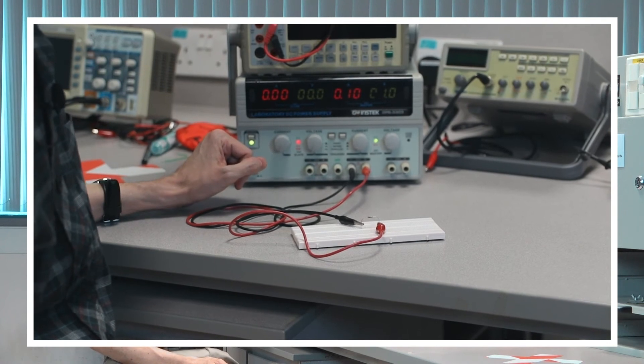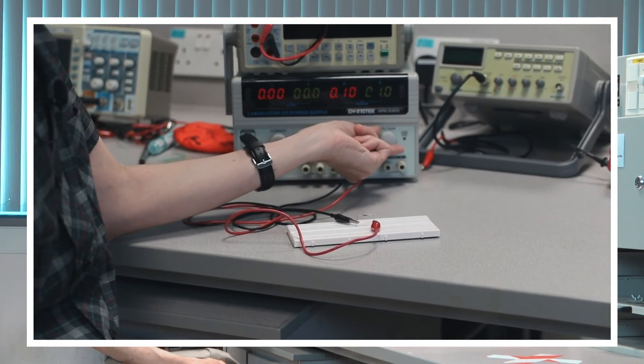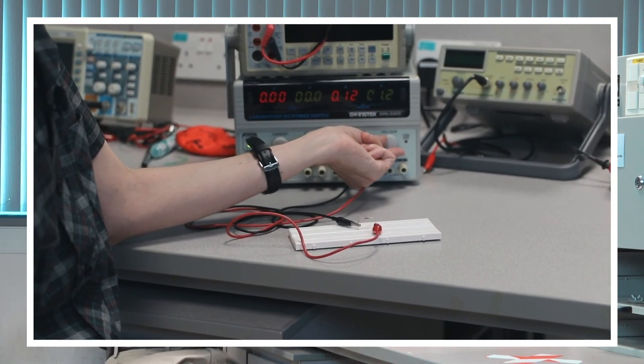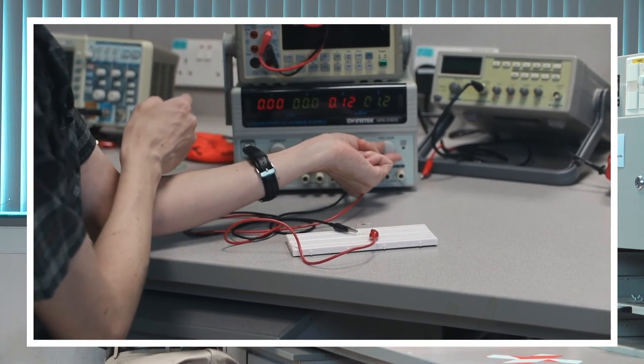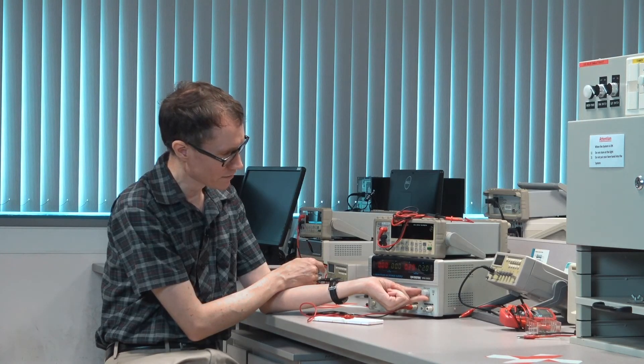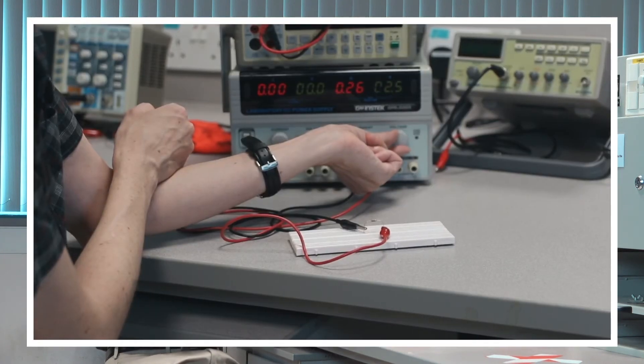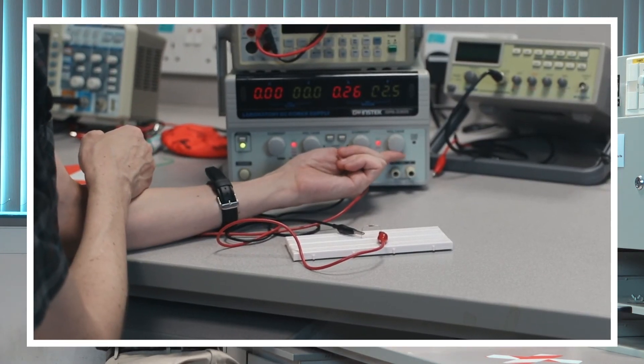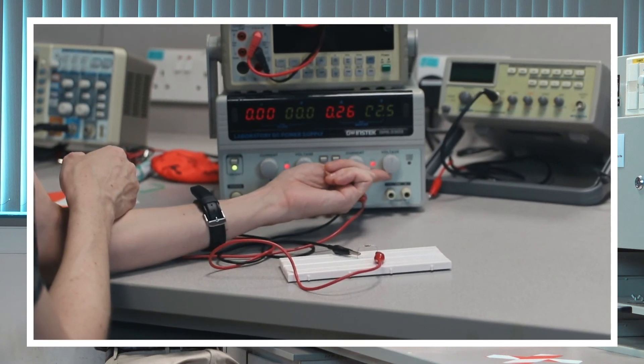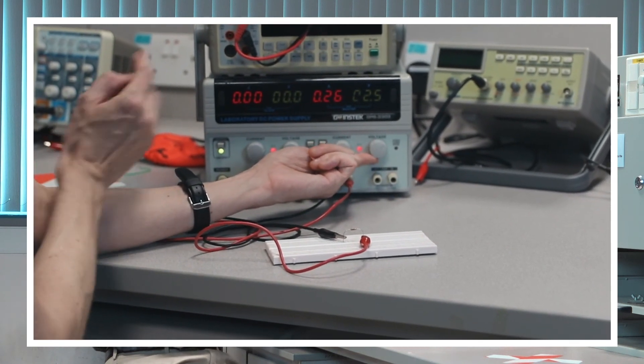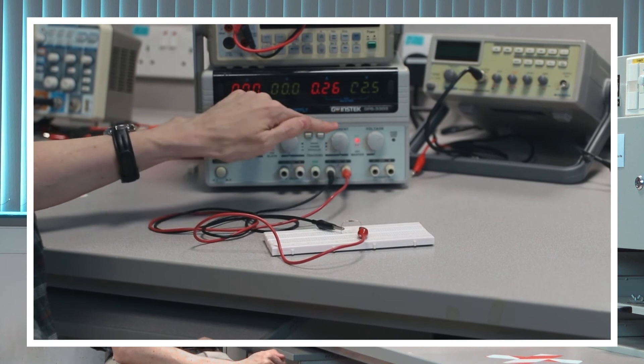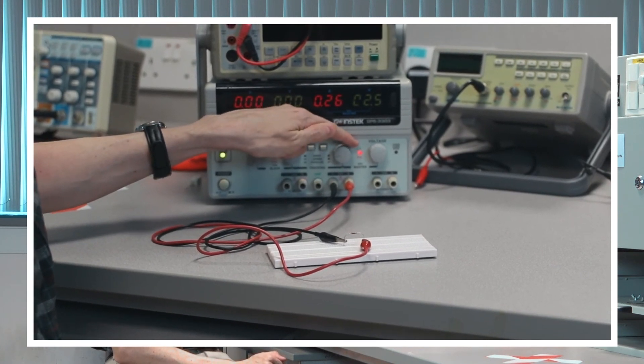If I try to increase the voltage for a while, the current will increase too. But when I get beyond my limit, the current will stop increasing. You see, now as I turn the voltage knob, nothing happens. As I continue to increase the voltage, everything is kind of clamped. And this color here has changed from green to red, indicating some sort of a problem.